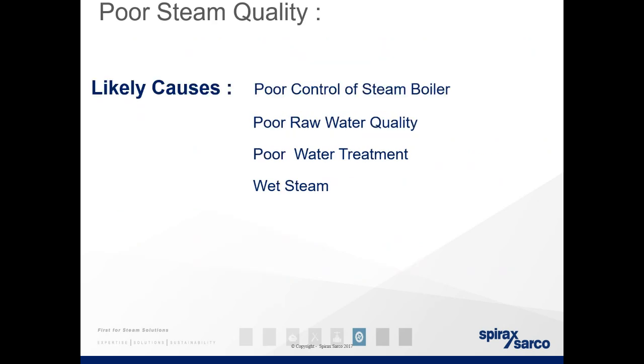So likely causes: it's poor control of the steam boiler. We spoke of, or touched upon, the carryover. Poor raw water quality. The more contaminants you have in your raw water making its way to your feed water, the more contaminants you can potentially have in your steam system. Poor water treatment, so faulty RO, reverse osmosis, or softener systems. And wet steam, from carryover or a buildup of condensate from improper trapping.